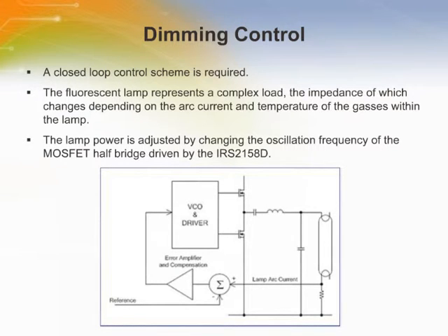The design of a dimmable ballast for the linear lamps requires that the lamp power can be reduced smoothly to allow a low output level, less than 5% of nominal lumen output. It is necessary that the lamp output is able to be held at any level and that there be no discernible flicker or instability at any level. The fluorescent lamp represents a complex load, the impedance of which changes depending on the arc current and temperature of the gases within the lamp.